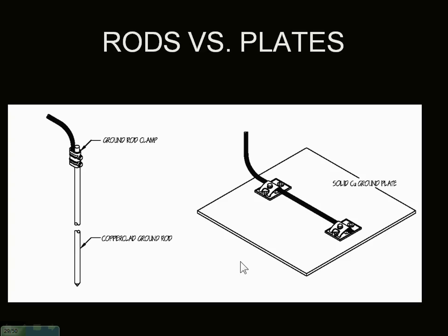The electrical code requires you to have 25 ohms or less. And if you can't maintain 25, you have to drive another ground rod. That's all they say. So there's more to grounding and bonding, and that gets transferred over to us.